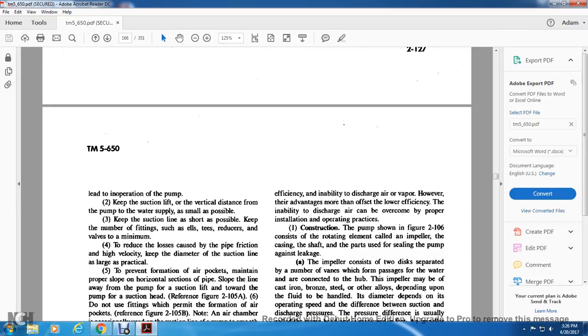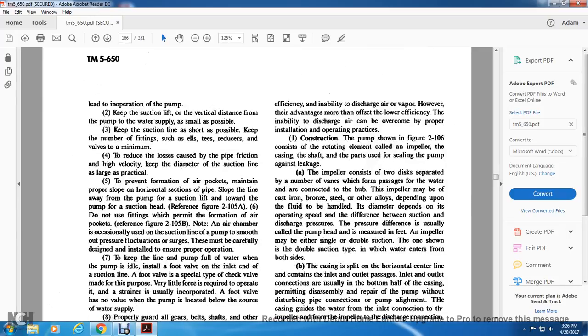Figure 2-104. Alright, two, keep the suction lift, the vertical distance from the pump to the water supply, as small as possible. Three, keep the suction line as short as possible. Four, keep the number of fittings such as elbows, tees, and reducers, and valves to a minimum. Five, to reduce the loss caused by pipe friction at high velocity, keep the diameter of the suction line as large as practical. Six, to prevent formation of air pockets, maintain the proper slope of the horizontal sections of pipe, sloping the line away from the pump for a suction lift and toward the pump for a suction head. Reference figure 2-105A.